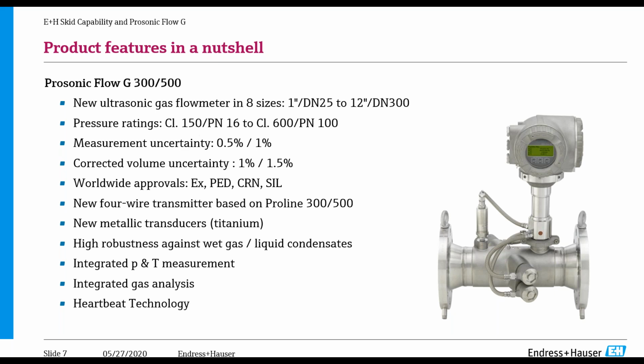to calculate the flow rate. So the new product we have is the Prosonic Flow G 300/500. It was just sales released earlier this year. We have it in size ranges from 1 inch to 12 inch, so that's 8 different sizes in between there. And we have a pressure rating of class 150 or class 600. The measuring uncertainty is 0.5% with our premium calibration. That's a 5-point calibration, or with a standard 3-point calibration, it's 1%.